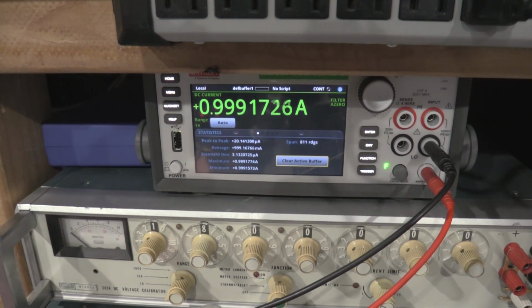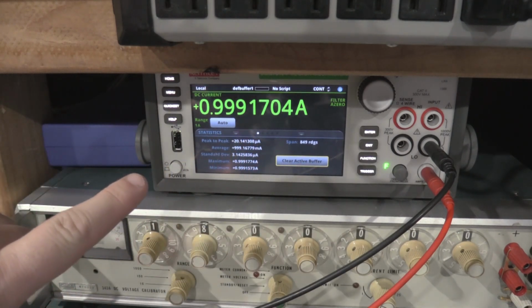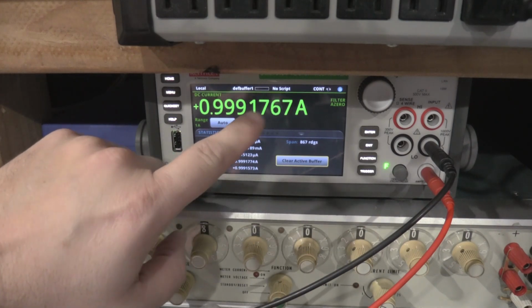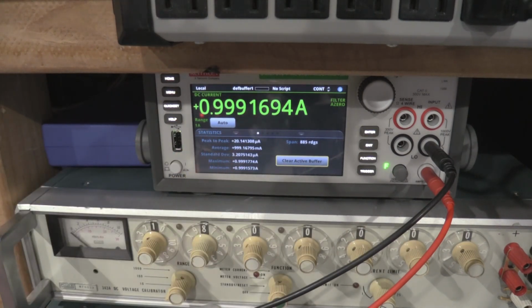Now, if anybody thinks the Keithley might be kicking it out of calibration, we're even giving it a hand because I'm putting 700 microvolts more voltage into the front end than I am. So this should be about 700 microvolts or 700 microamps higher than it is, and so we are still off. We will unplug the meter just to be safe. We'll just pop the meter out of circuit. Nothing really changed, although we got a little bit of action on here while it settled, but then it settled back down, so the meter impedance wasn't causing it any heartburn. So we do have a unit that needs adjustment. Not a problem. We can do the adjustment. I just need to get shunt resistors.